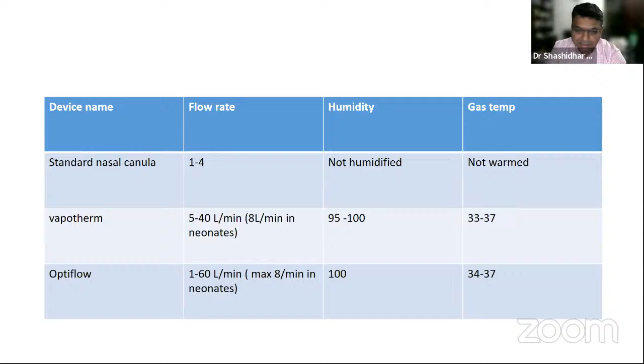After covering the physiology and how we do it, there are certain do's and don'ts of nasal high flow therapy. The most important thing is we should not completely cover the nasal orifice with the tube. The prongs should cover around 50%, definitely not more than 80%. That's very important because there should be a leak. Whereas in CPAP, leak is a problem, in heated humidified high flow therapy, leak is required for effective functioning of the high flow.